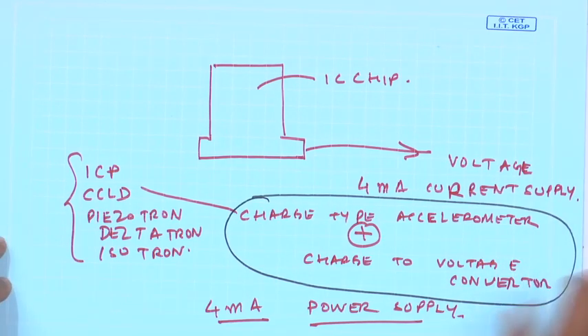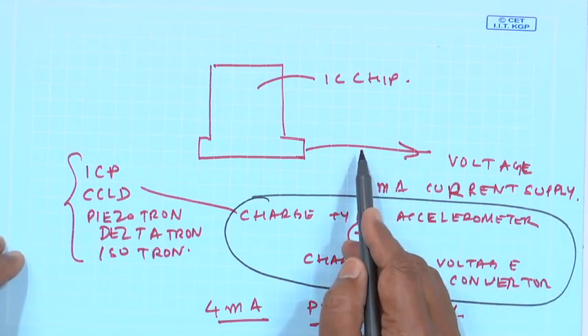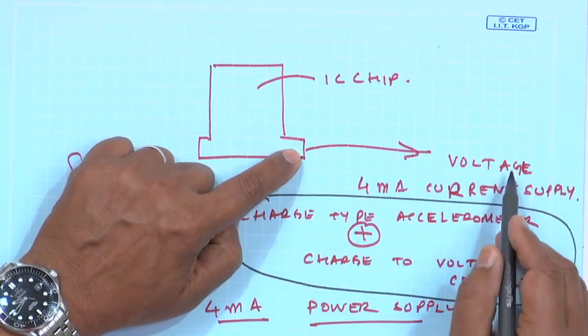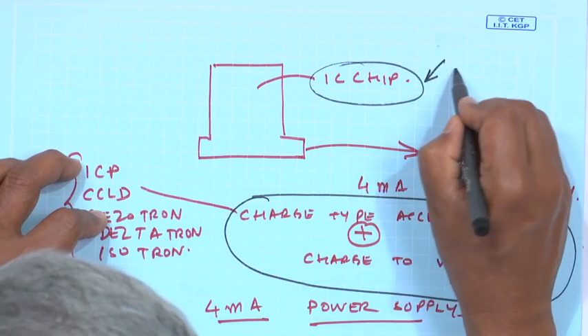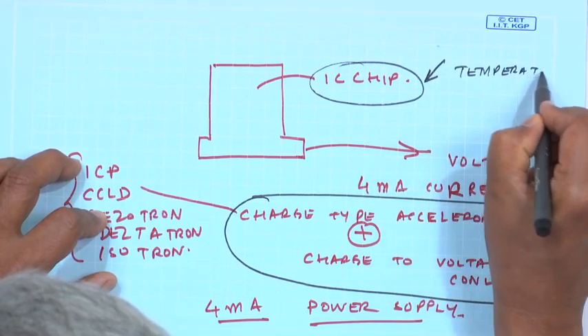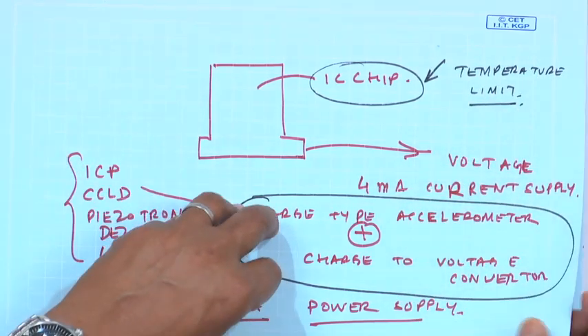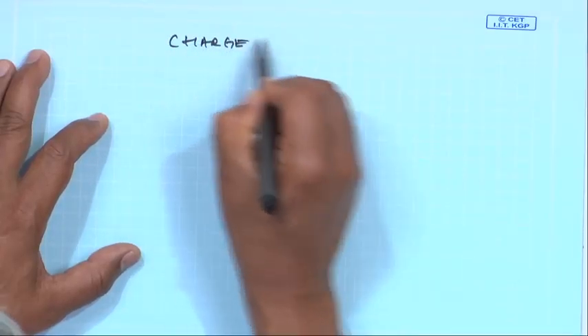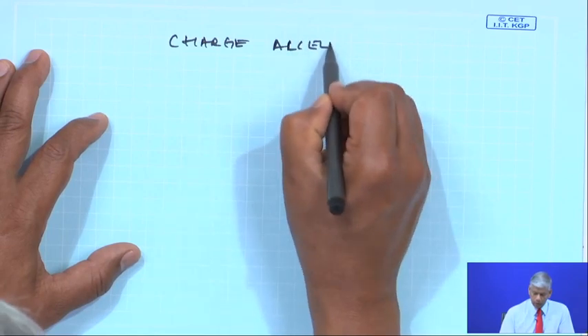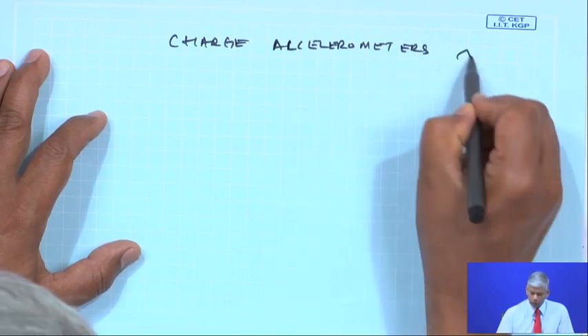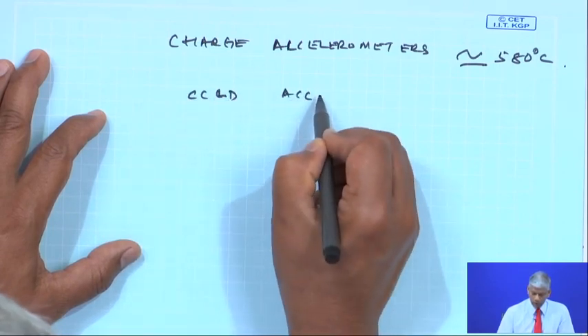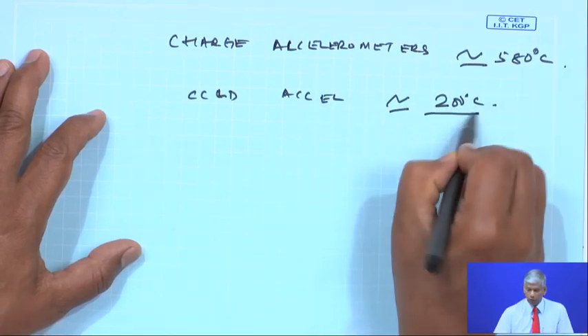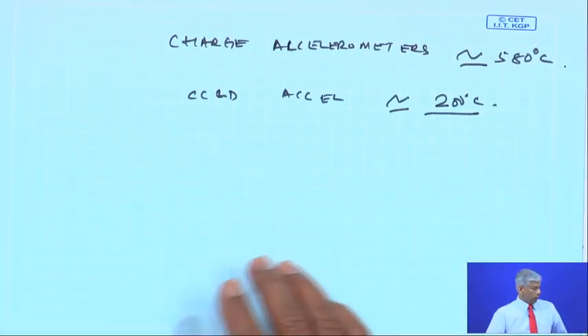The advantage of built-in converters is you do not need to carry a separate charge-to-voltage preamplifier or power supply. The voltage output can be connected directly to a signal recording unit. However, there is a temperature limitation because the IC chip is inside. Charge-type accelerometers can operate up to around 580 degrees Celsius, but CCLD accelerometers can only go up to about 200 degrees Celsius. For high-temperature applications, charge-type accelerometers are required.